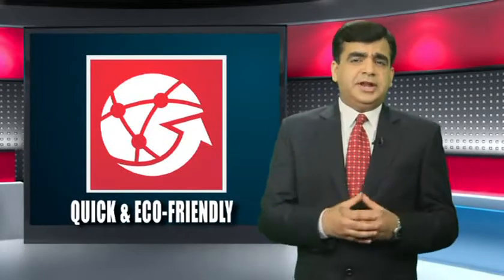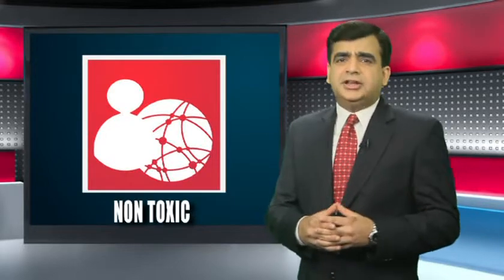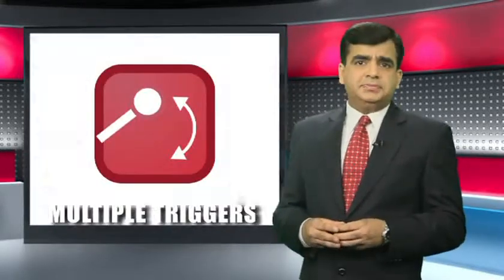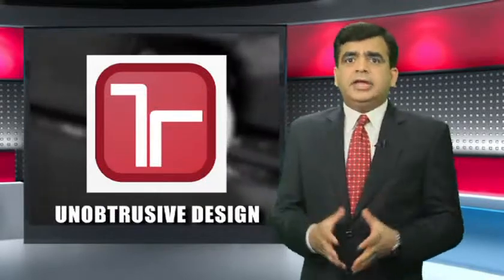Quick and eco-friendly, dry mist's non-toxic nature ensures that operations will be up and running quickly. This system is always on, all the time, and has multiple triggers. Designed to be unobtrusive, it maintains the aesthetics of the facility. Dry mist is perfect for theatres, server rooms, storage spaces, and parking lots. It may be a low-pressure system, but the dry mist system puts a lot of pressure on fire.